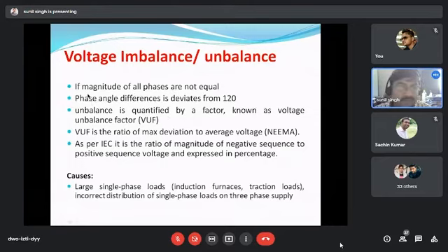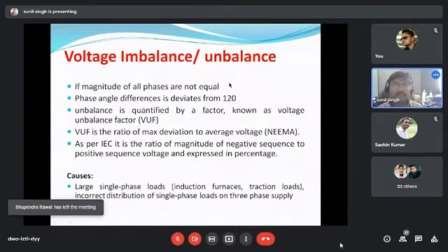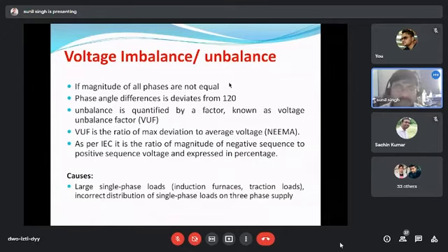Let us discuss what voltage imbalance or unbalance is. In the literature it is sometimes written imbalance and sometimes unbalance. So what is the definition of voltage imbalance? As we know, three-phase power should have equal magnitudes and equal phase differences of 120 degrees. If this is not so, it is known as a voltage unbalance or voltage imbalance problem.